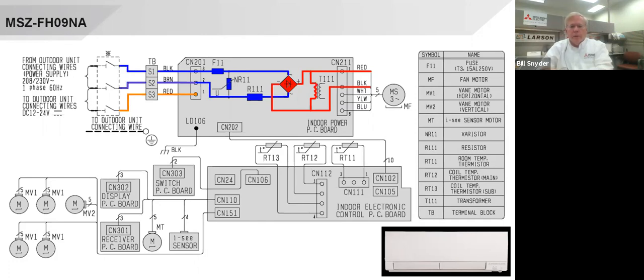internal of the unit. These RTs are your thermistors. In this case, they're labeled RT, and the other diagrams, I think they're TRs, but they're thermistors in here. And this motor right here is the i-See sensor motor, I believe. Yeah, i-See sensor motor here. That's a little sensor that rotates throughout the room and scans the room and looks at temperatures within the room.